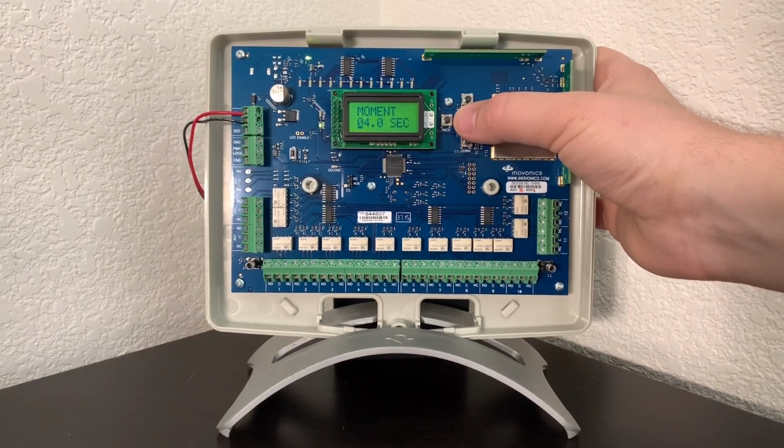We'll set alarm 2 up for momentary as 4 seconds. Alarm 3 to output 6, set up as a toggle option. And the inactive time for that toggle option will be 4 seconds. And then alarm 4 going to output 7, set up as a latching condition. We'll go through our trouble condition options, enter through our text, and register the transmitter.